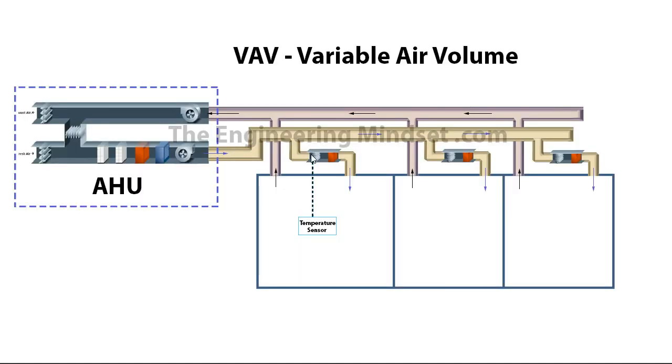Now if you imagine these VAV boxes which are connected to the system here, as they can all vary the amount of air which is coming and filling into the space before being returned to the AHU, as they vary that amount of air, then these dampers will start to close.